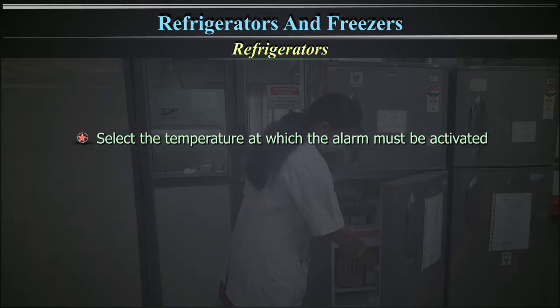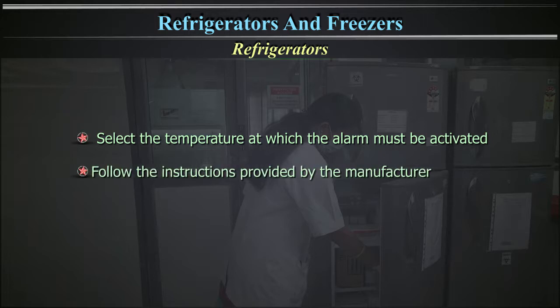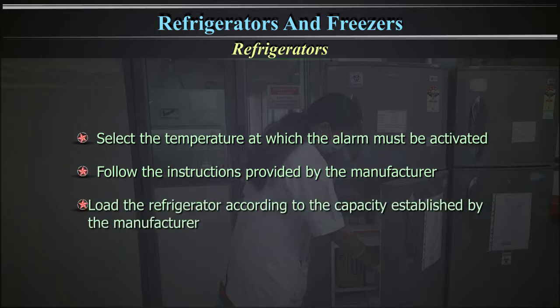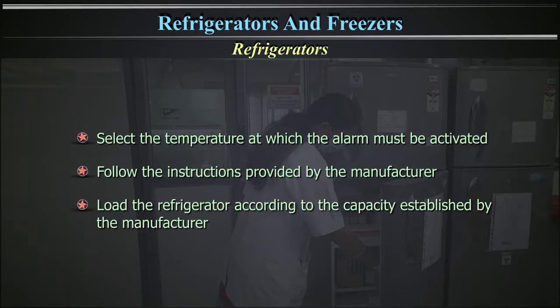3. Select the temperature at which the alarm must be activated. Follow the instructions provided by the manufacturer. 4. Load the refrigerator according to the capacity established by the manufacturer.